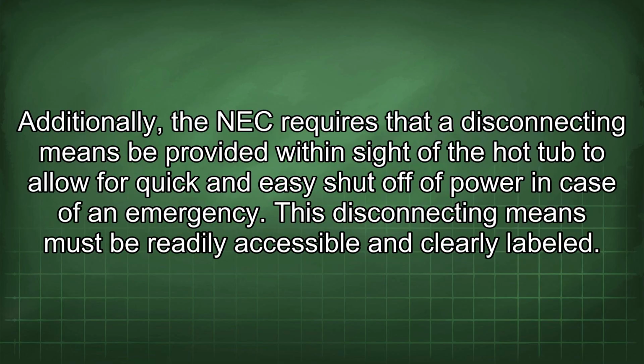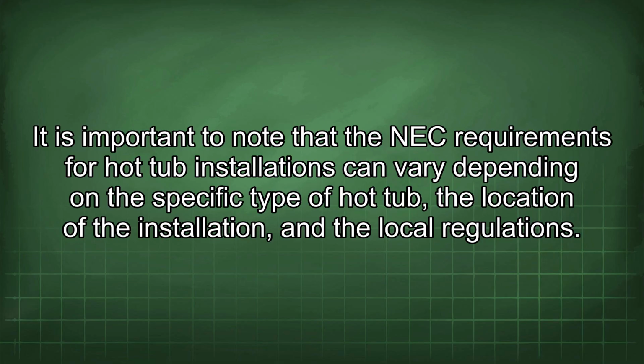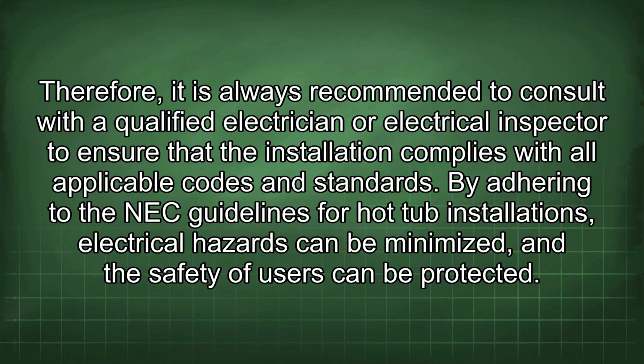Grounding conductors must be sized and installed in accordance with the code to ensure effective protection. Additionally, the NEC requires that a disconnecting means be provided within sight of the hot tub to allow for quick and easy shut-off of power in case of an emergency. This disconnecting means must be readily accessible and clearly labeled. It is important to note that the NEC requirements for hot tub installations can vary depending on the specific type of hot tub, the location of the installation, and the local regulations. Therefore, it is always recommended to consult with a qualified electrician or electrical inspector to ensure that the installation complies with all applicable codes and standards.